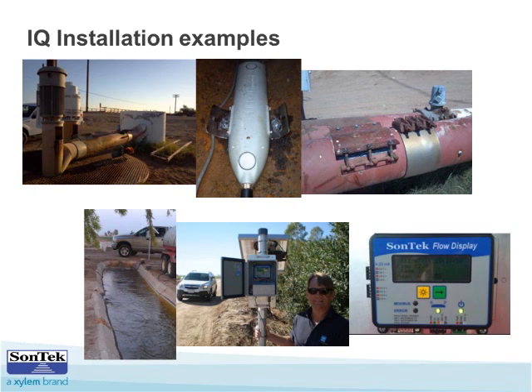How about this one: is the data assigned to the start or the end time of the measurement interval? Either way works—you need to either time it to start at the top of the hour, or time the sample to be output at the top of the hour, and then tell it how long you want it to average, and the instrument knows how to do that.